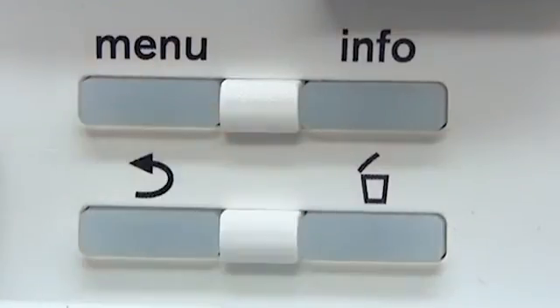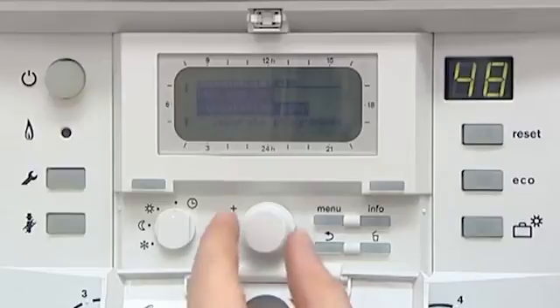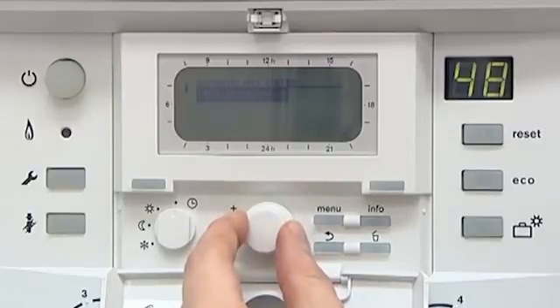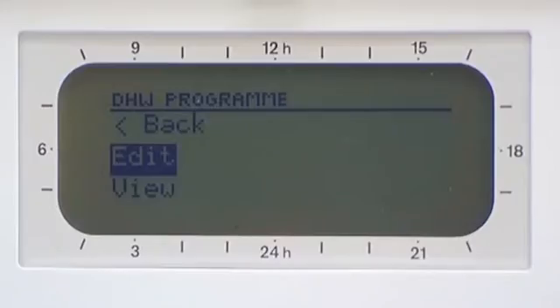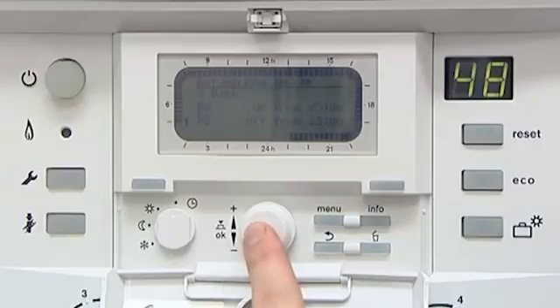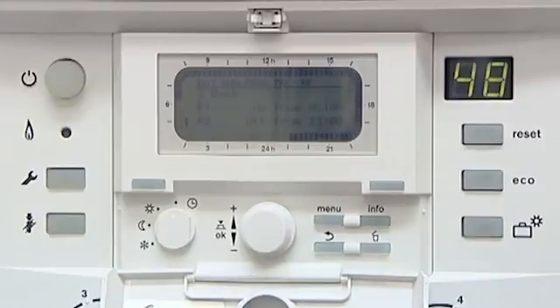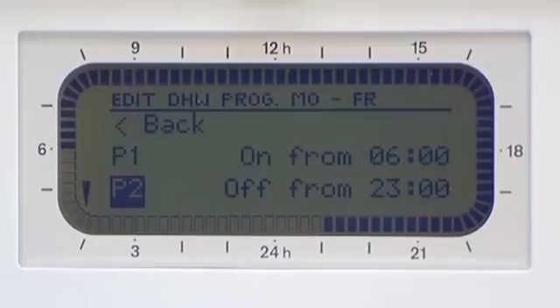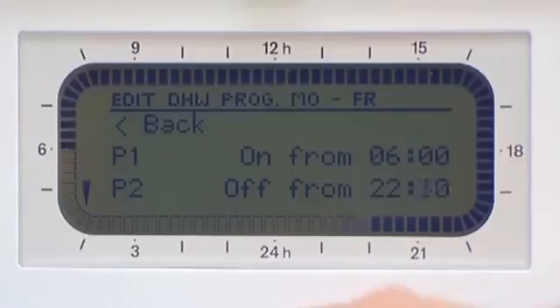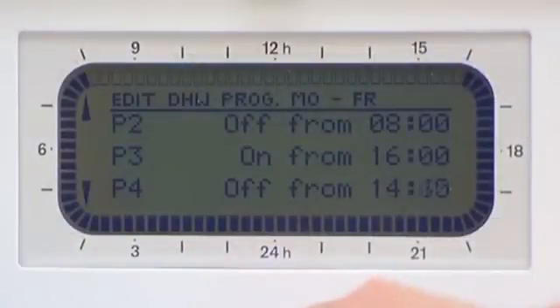Press Menu. Scroll down to Domestic Hot Water and press OK. This allows you separate programmes. Scroll down to Domestic Hot Water Program and press OK. Select Edit, then select Monday to Friday. Select P1, which is set at the factory setting — in this instance we will reset to 6am. Press OK. Then select P2 and reset your off time. Select P3 to set the time when your pre-heat facility will come back on, and P4 when you would like it to turn off.